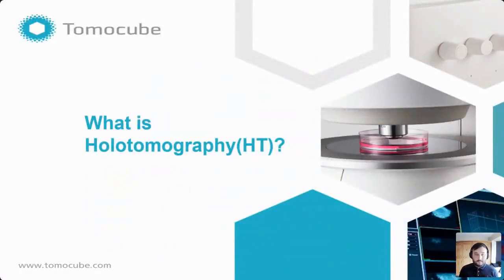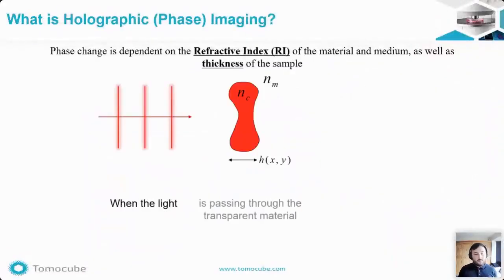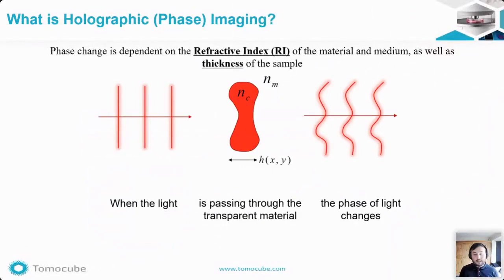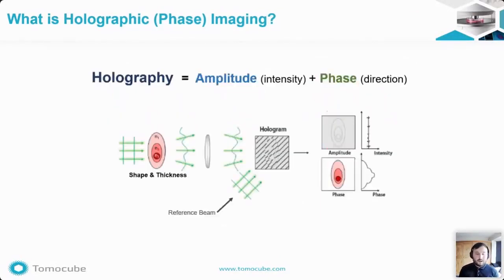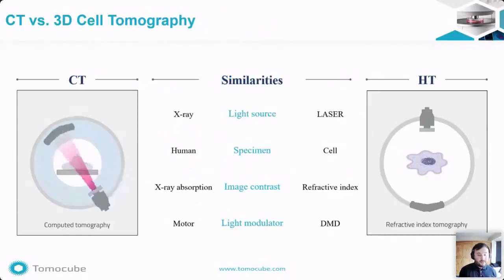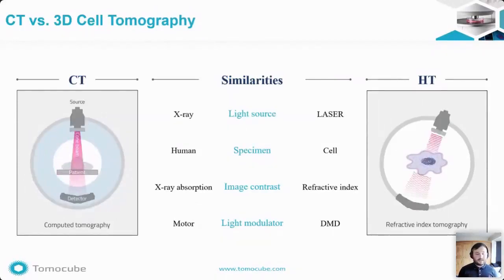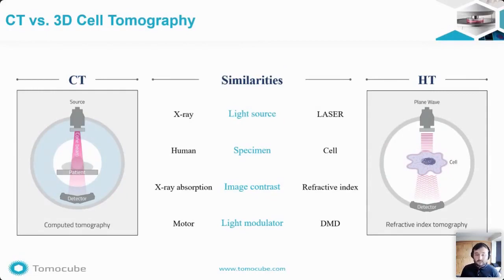So what is holotomography? It is a form of QPI. The principle is to detect the changes in the phase of light as the light passes through the material — in our case, the cell. Holography is achieved using the amplitude and the phase. However, a single hologram only provides a 2D image. So in order to generate the 3D image, we rotate the light beam around the specimen, as in a CT scanner. The light path itself is not mechanically moving around the sample, but the light is reflected in a manner that covers 360 degrees of the cell.